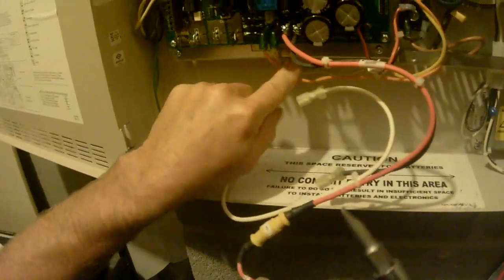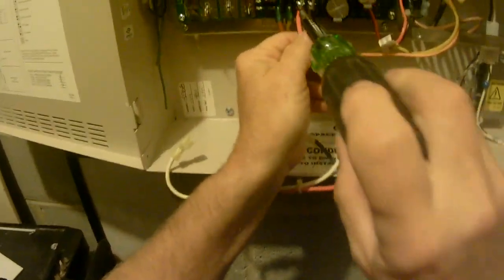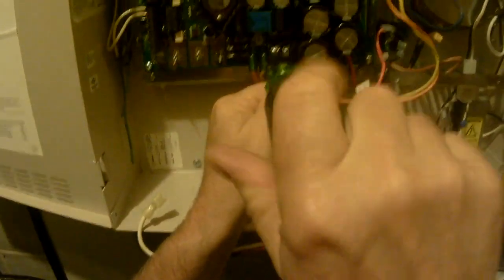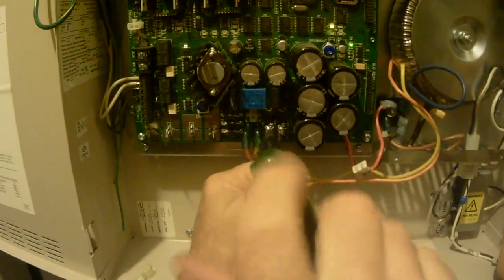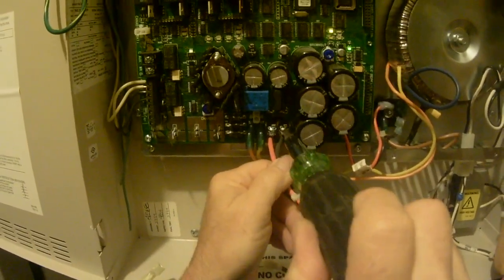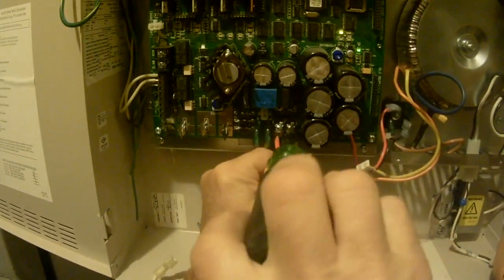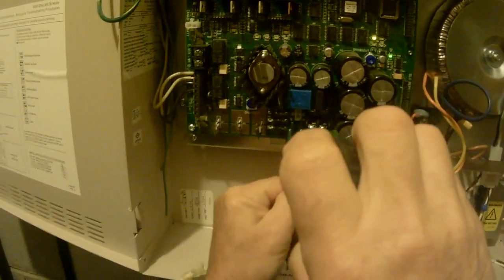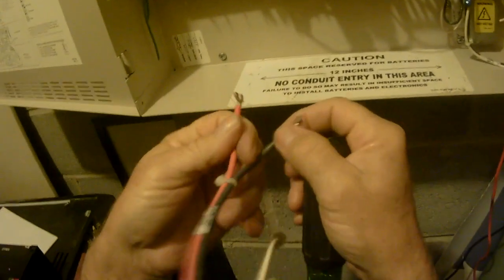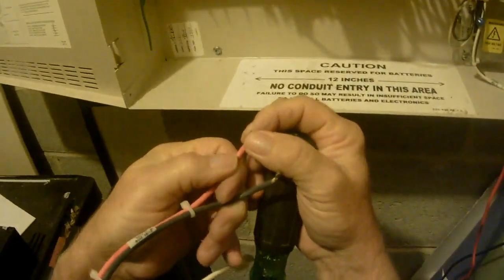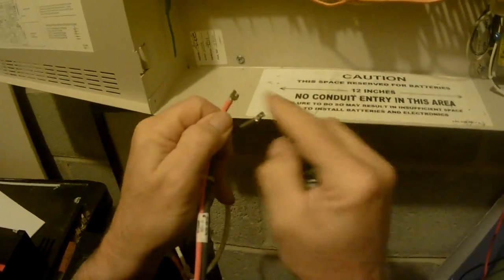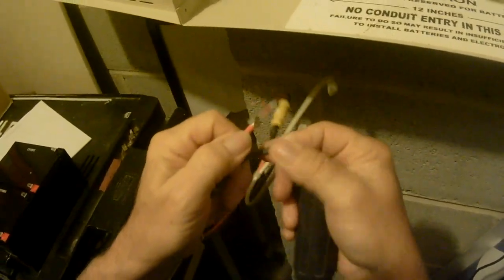Now here's one other thing that I like to do while I'm changing these batteries out. I like to check these screws because a lot of times they're loose. A lot of times these screws are loose. The thing is, the way Simplex, the factory, wires these, they strip these things out real short. They're barely long enough to go into the screw there and they're on one side of the screw.